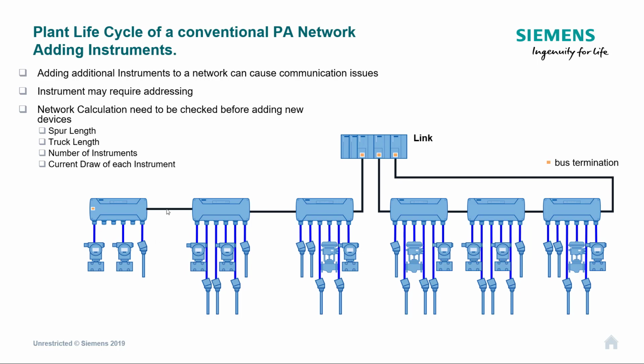Okay, we need to get that plant up and running, and we've put it on, and a lot of the times you can get away with it until you add something else on at a later date, and then you start to have network issues. So what we've got to do is try and find a solution that is a lot more stable and simplifies Profibus PA, takes away all of these issues with network design.